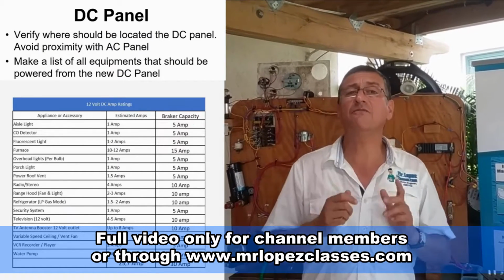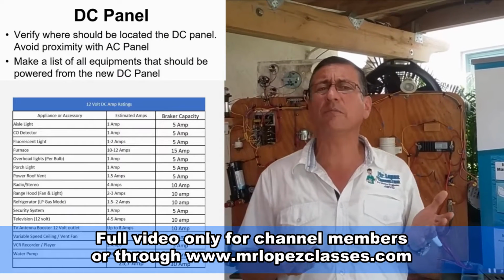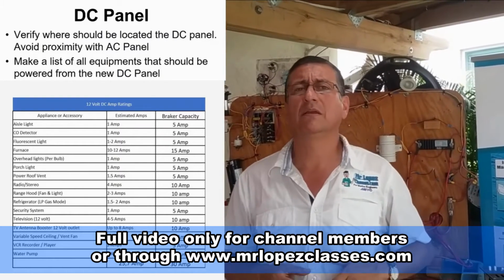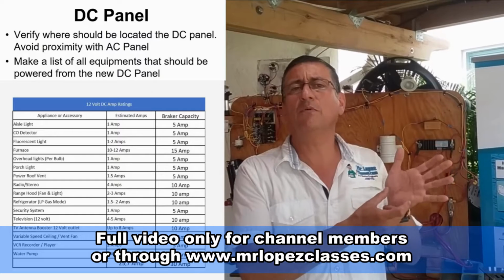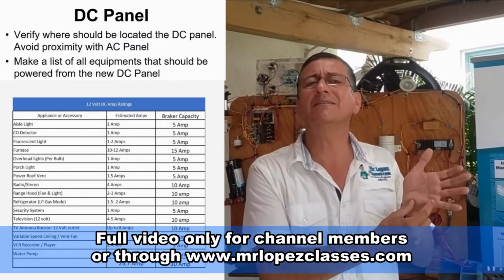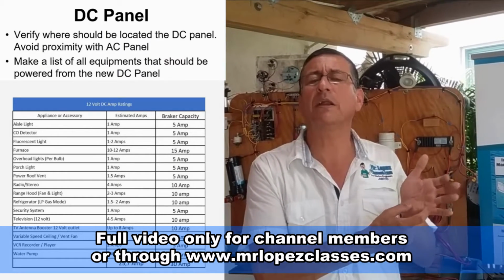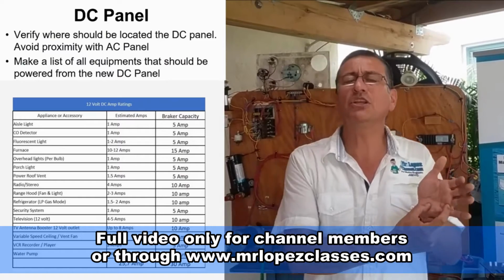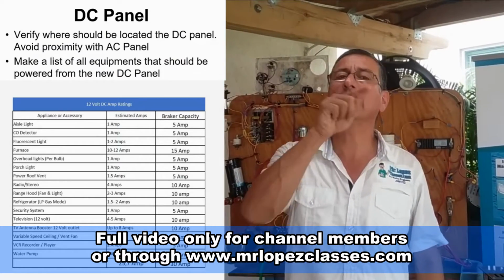Where is that information located? In the label of the equipment. The label says the voltage and the intensity, the consumption in amps per hour. With that consumption, you select the breaker for that equipment.